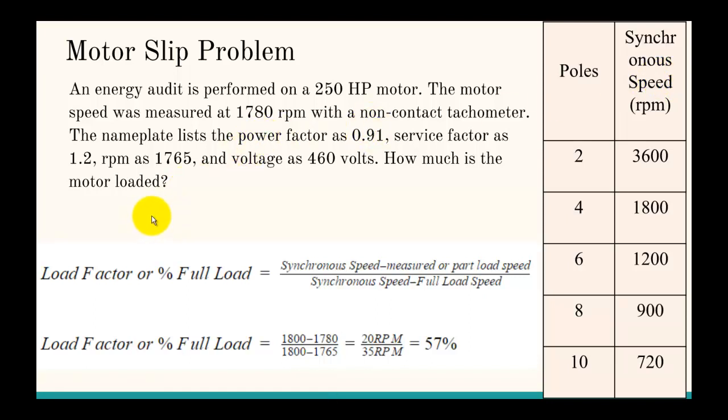Now let's talk about how you figure out load factor from that. You basically use something called the slip method. It's how much it slips at part load versus full load. We take the synchronous speed, which is the 1800, subtract what the measured or part load speed is, which we measured at 1780. That's the numerator. The bottom is the synchronous speed minus the full load speed, which is normally listed on the nameplate, which is 1765. Then we take the ratio of those two and we find that it's 57% loaded. So if it asks what horsepower the motor was outputting, you would take this 57% and multiply by the 250 HP. So those are the motor and pump and fan problems. Thanks for watching.